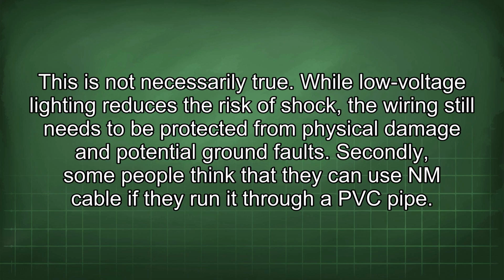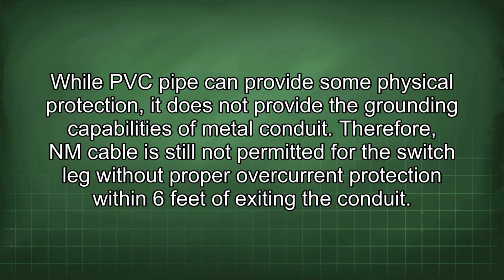This is not necessarily true. While low voltage lighting reduces the risk of shock, the wiring still needs to be protected from physical damage and potential ground faults. Secondly, some people think that they can use NM cable if they run it through a PVC pipe. While PVC pipe can provide some physical protection, it does not provide the grounding capabilities of metal conduit. Therefore, NM cable is still not permitted for the switch leg without proper overcurrent protection within 6 feet of exiting the conduit.